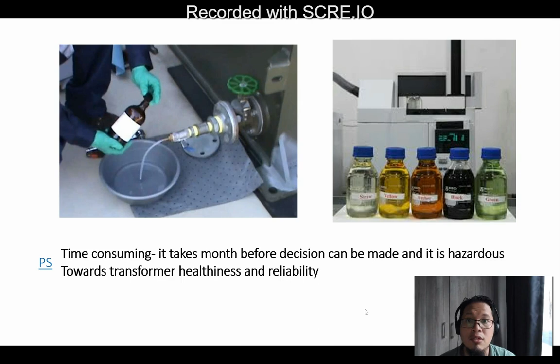When you consider substations, they are normally crowded with internal and external noises. It can be wide or random noise that varies throughout the frequency band. With internal or integrated sensors, false alarms can happen, and this is something we want to prevent, because a false alarm means we have to shut down the transformer without any actual problem, just because of a sensor issue or an uncalibrated sensor.